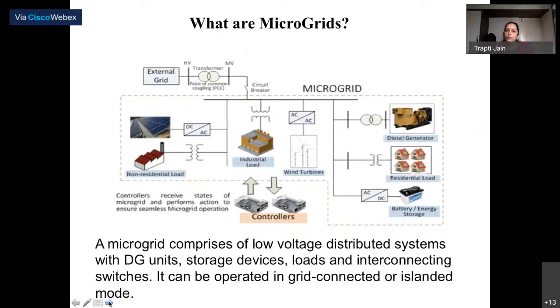These two modes of operation provide us flexibility. Suppose you see in the diagram, one circuit breaker is shown near the microgrid, and then the external grid is there. So the point of common coupling, PCC, is there. This circuit breaker allows us to disconnect the microgrid from the external grid whenever there is a fault in the external grid, so that fault cannot propagate into the microgrid. By disconnecting, we can still supply uninterrupted power to our consumers.